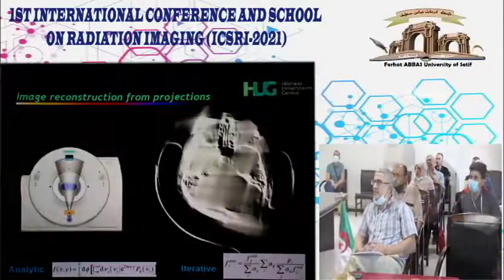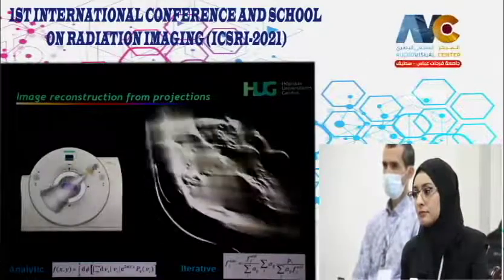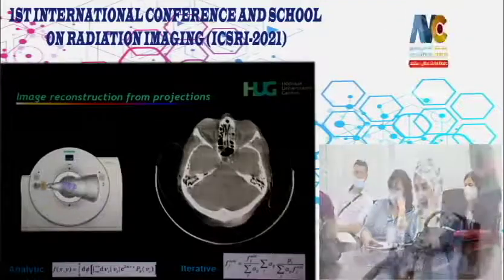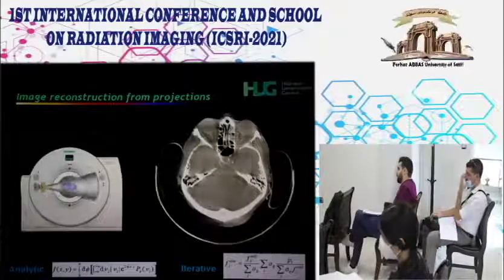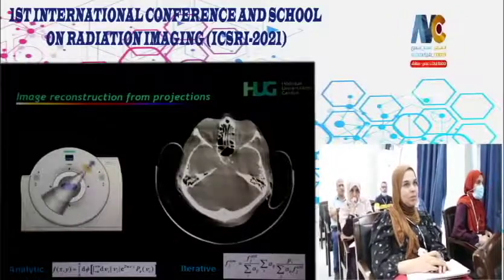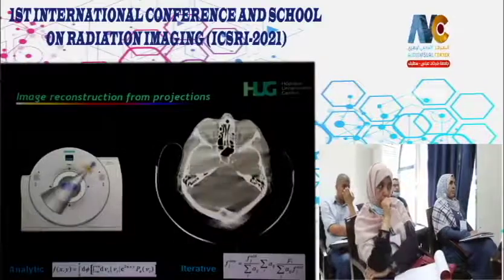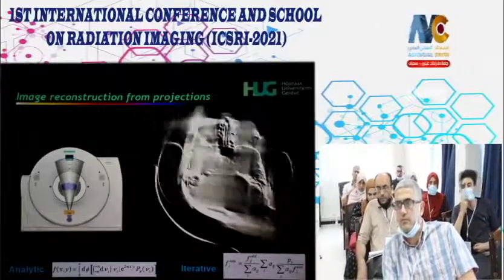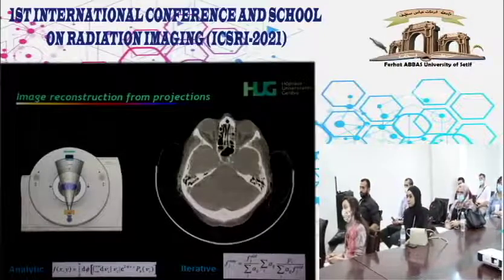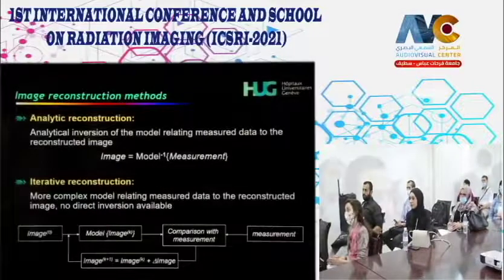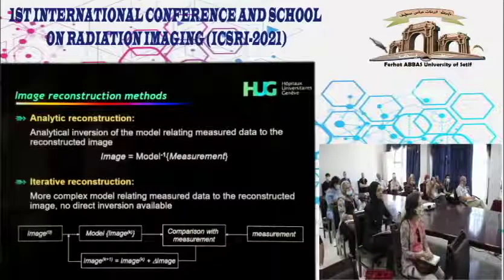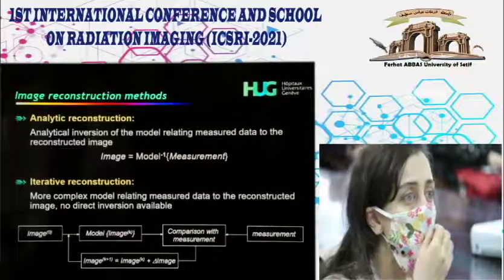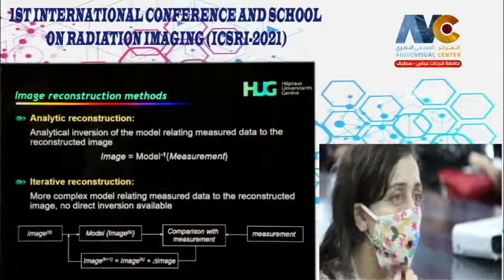Image reconstruction from projections inverts the acquisition process. Filtered back projection filters the acquired projections in Fourier space and then back-projects them line by line to display the image. The analytic approach is the exact inversion of the Radon transform or x-ray transform depending on the acquisition model, inverting the measured projections to get images.